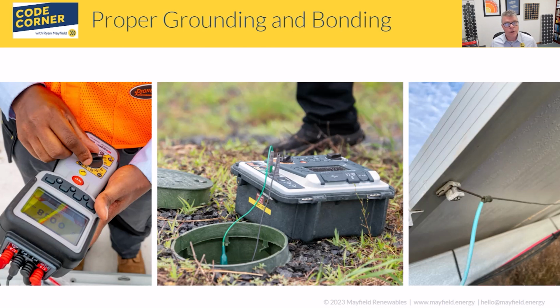What you're looking at there in the middle is the digital earth tester. If you are at a larger site, in substations, you don't even have to have substations, but if you have a larger site and a grounding system that you need to verify, and you need to check what that resistance is to earth, using a digital earth tester is a way of doing that. There are multiple ways of using it. There are fall of potential tests that could be done with it. And so again, it depends on the scale that you're at.